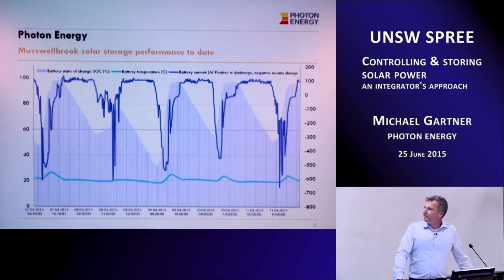Now this is just to show you how the charging and discharging cycle is working. The dark blue line shows what's happening on the charging end of things - you can see the amount of charge current we're putting into the batteries is about 7 times the output current, so we're charging the batteries quite fast. That's the nature of solar power: it's got a lot of power in the middle of the day, a reducing curve in the afternoon, and an increasing curve in the morning.